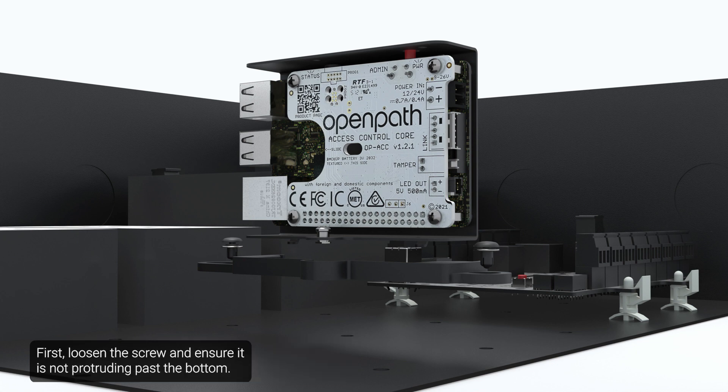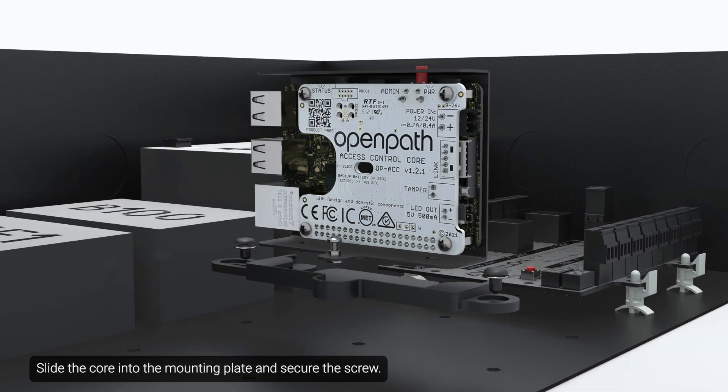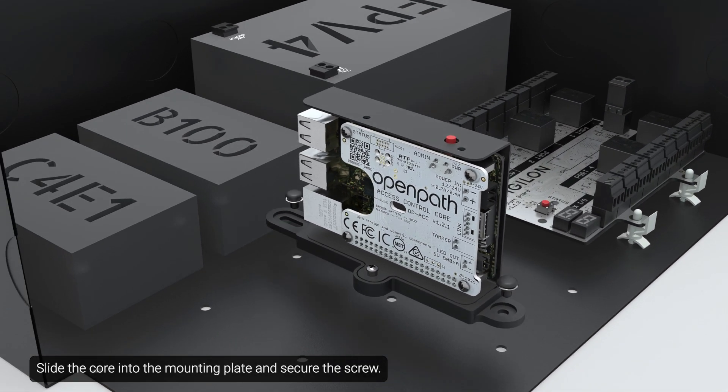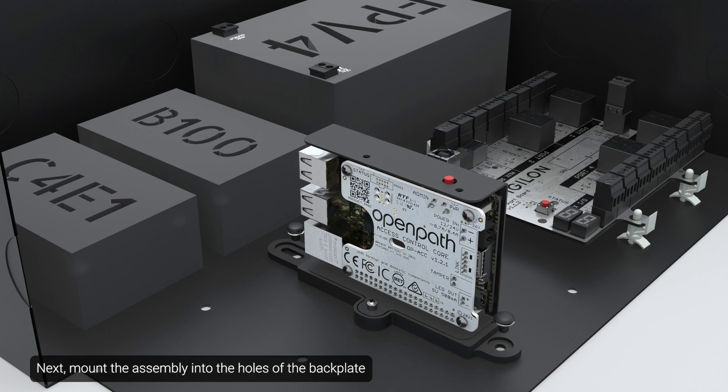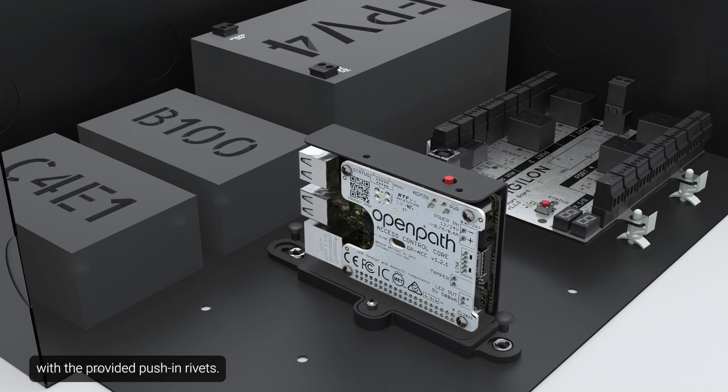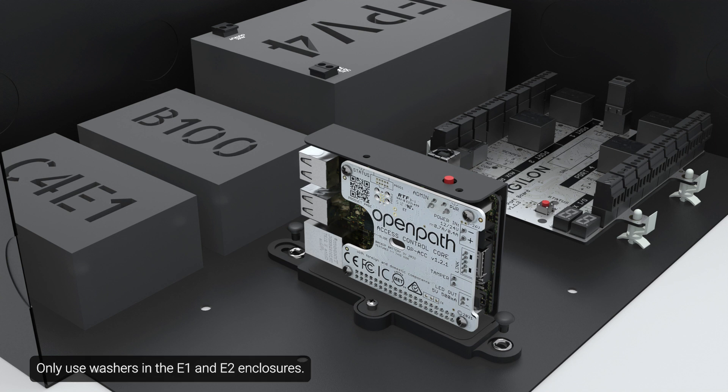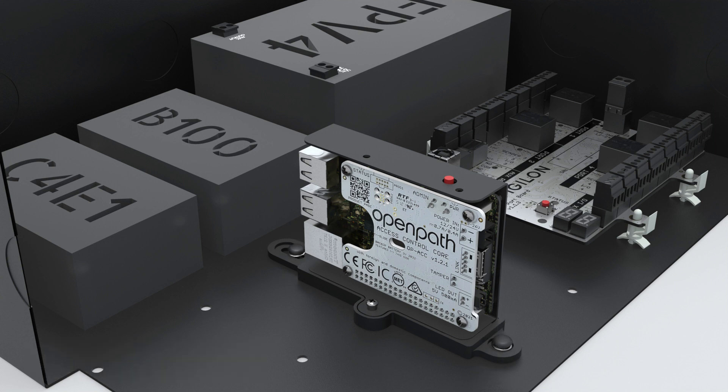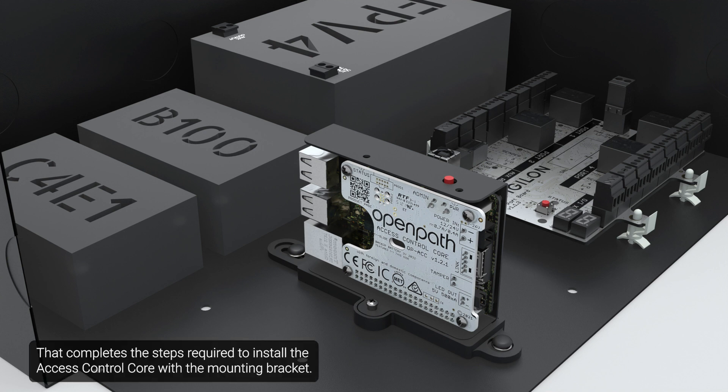First, loosen the screw and ensure it's not protruding past the bottom. Slide the core into the mounting plate and secure the screw. Next, mount the assembly into the holes of the back plate with the provided push-in rivets. Only use washers in the E1 and E2 enclosures. Washers are not necessary for the back plate in the E4 and E6 enclosures. That completes the steps required to install the access control core with the mounting bracket.